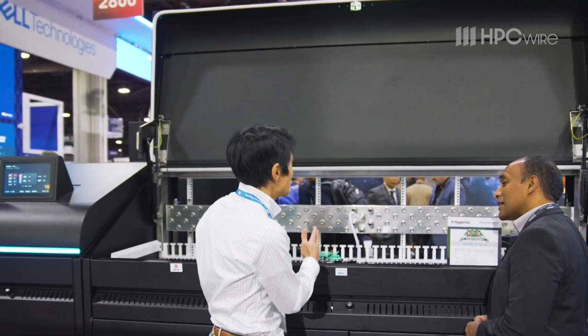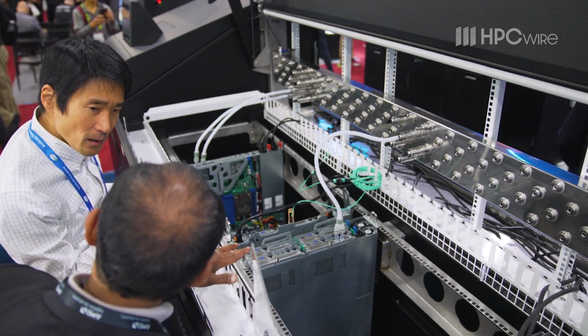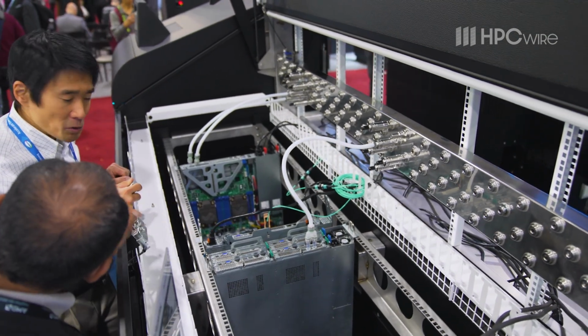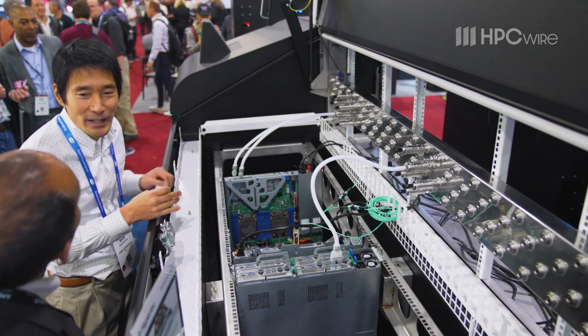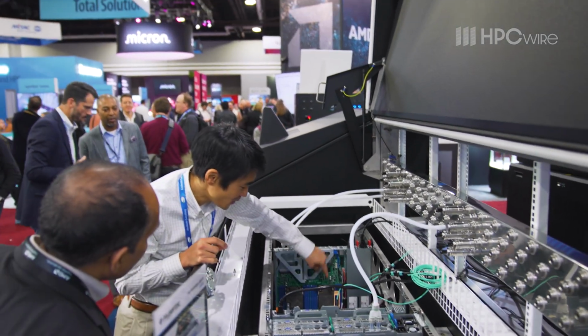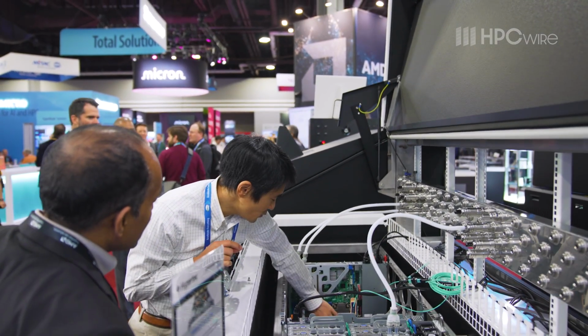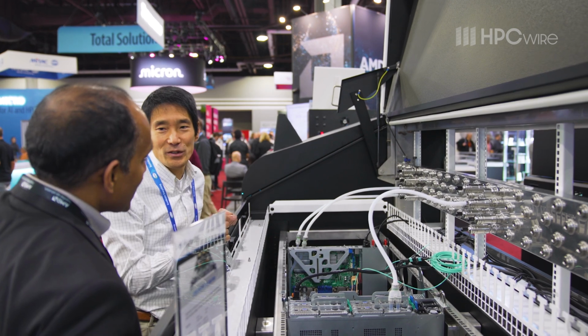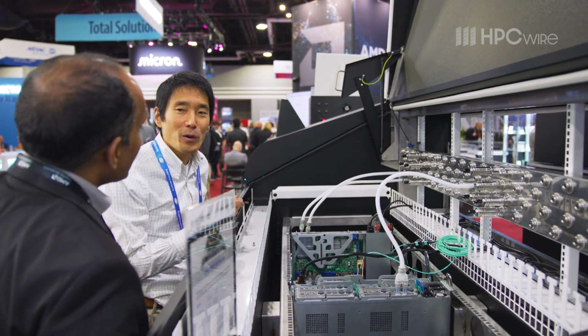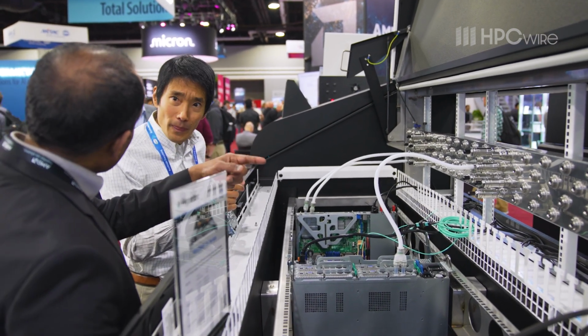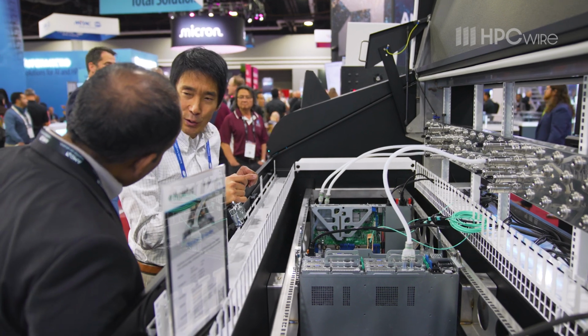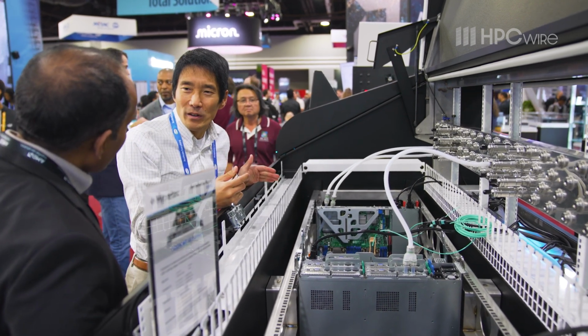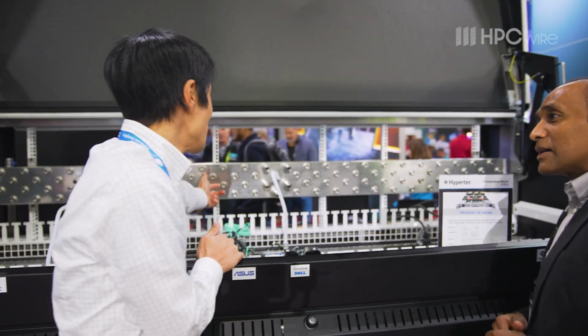That's essentially one tank, one CDU. The twin tank configuration is 2 CDUs, 2 tanks. The idea is that should one of those CDUs go down, the healthy one basically takes over for both tanks. In that situation, your thermal capacity gets reduced to about 250 kilowatts, but that's still really, really good, industry leading still. And then finally, the flexibility, I think, is what really sets it apart.